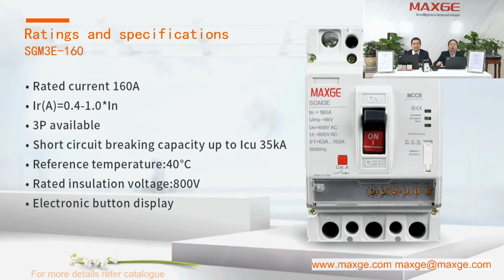The first one is the SGM3E-160 ampere frame MCCB. The rated current is 160 ampere, but the IR rating is from 0.4 to 1.0 IN. This is the key feature of our electronic type MCCB, that we have the long delay range from 0.4 to 1 IN, whereas if you see the competitors' MCCB, they may have from 0.6 to 1 IN, but our range is from 0.4 to 1 IN, which is very wide. Normally in the Gulf countries and Egypt, all the requirements fall towards 0.4 to 1 IN. Yes, the wide range also gives the customers more choice.